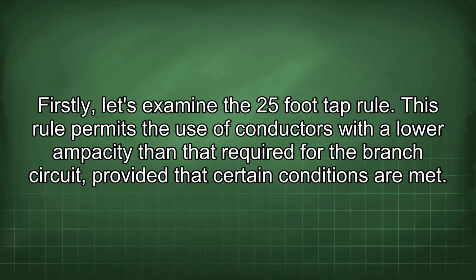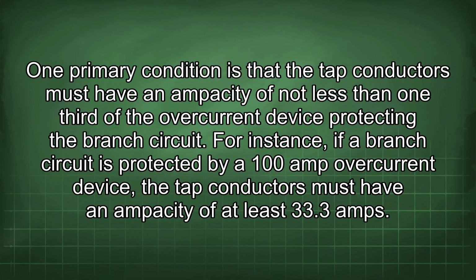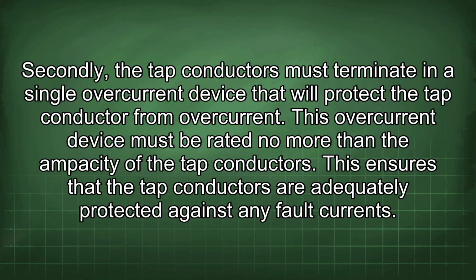This rule permits the use of conductors with a lower ampacity than that required for the branch circuit, provided that certain conditions are met. One primary condition is that the tap conductors must have an ampacity of not less than 1/3 of the overcurrent device protecting the branch circuit. For instance, if a branch circuit is protected by a 100 amp overcurrent device, the tap conductors must have an ampacity of at least 33.3 amps. Secondly, the tap conductors must terminate in a single overcurrent device that will protect the tap conductor from overcurrent. This overcurrent device must be rated no more than the ampacity of the tap conductors. This ensures that the tap conductors are adequately protected against any fault currents.